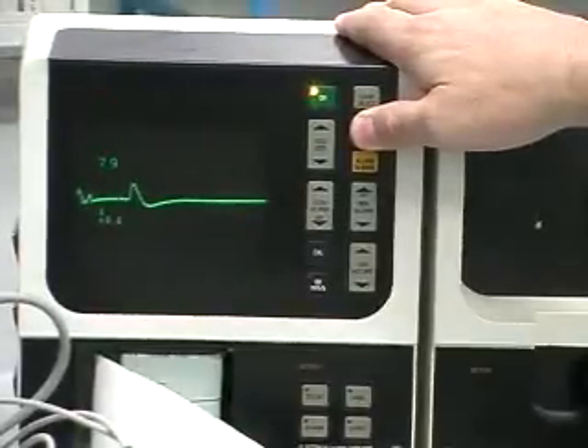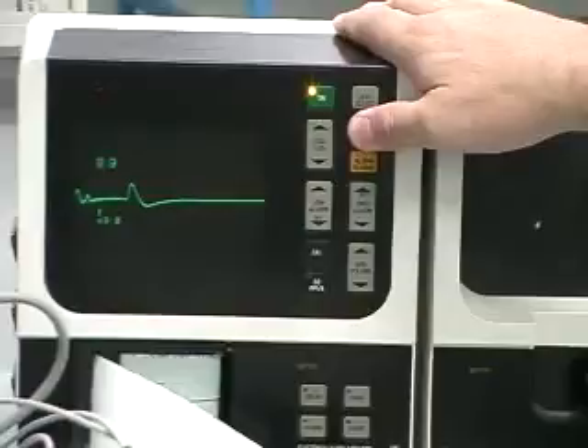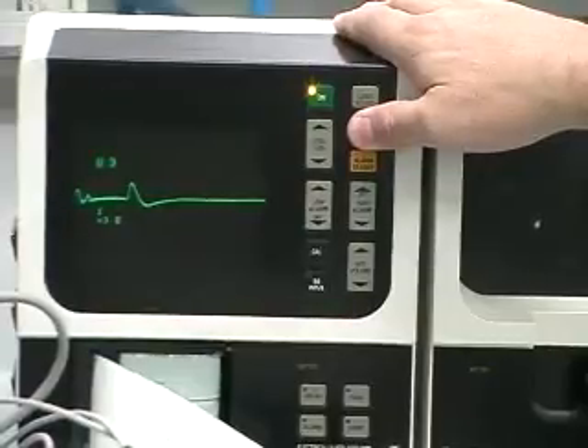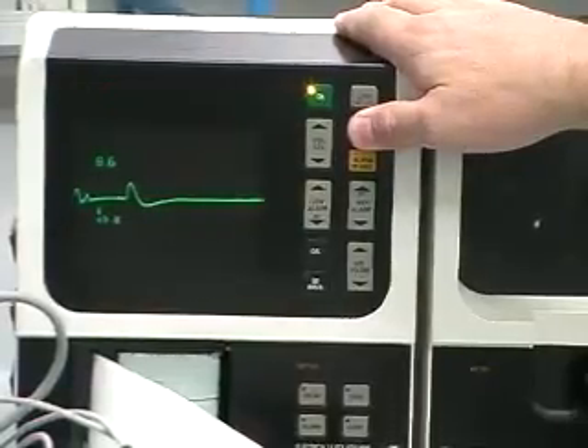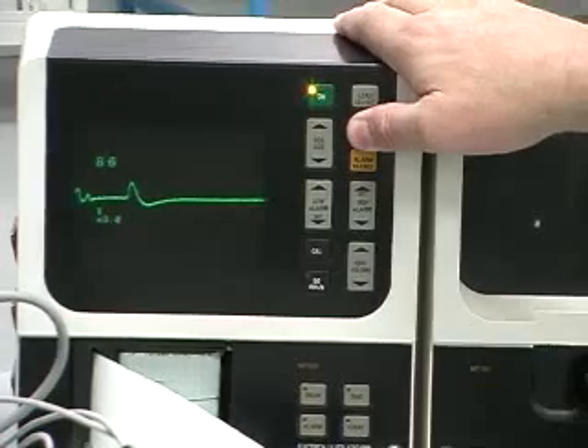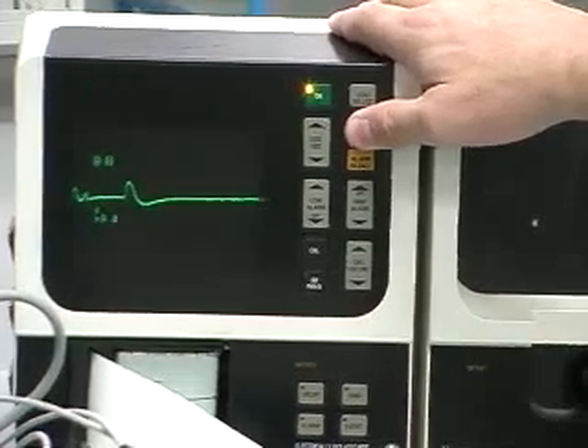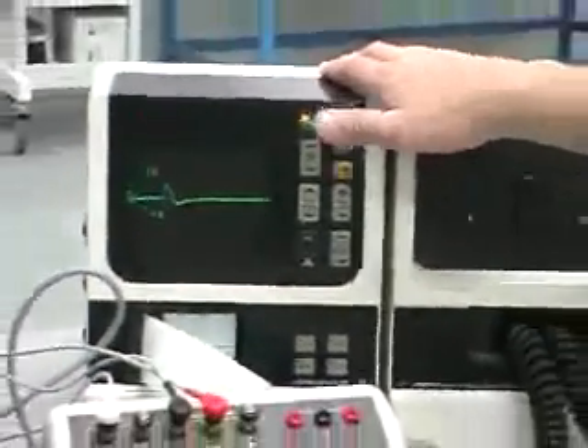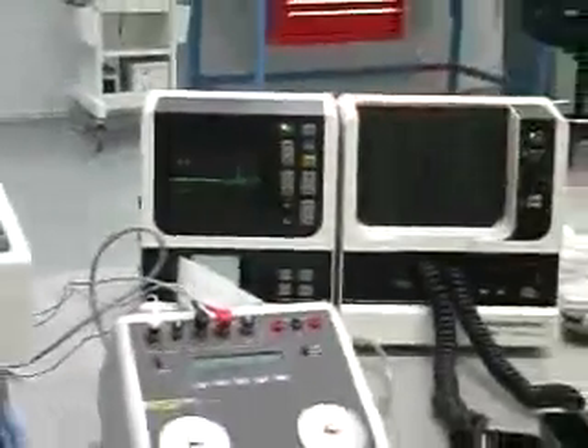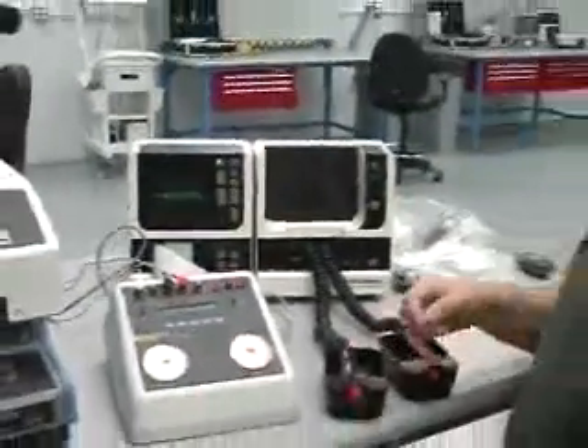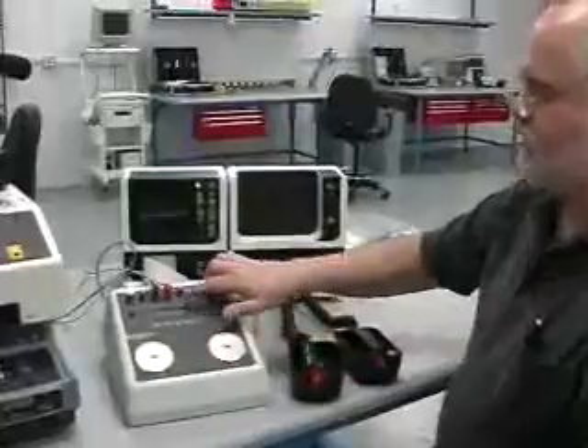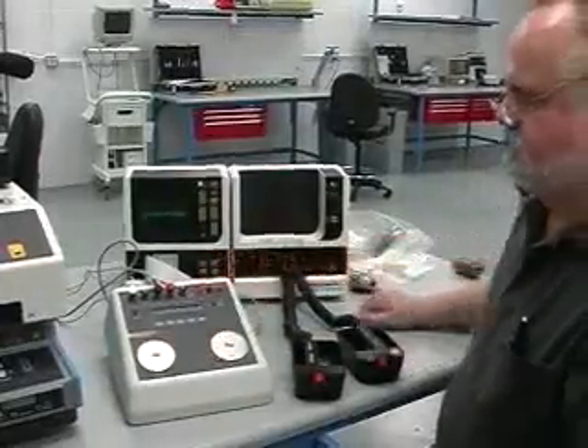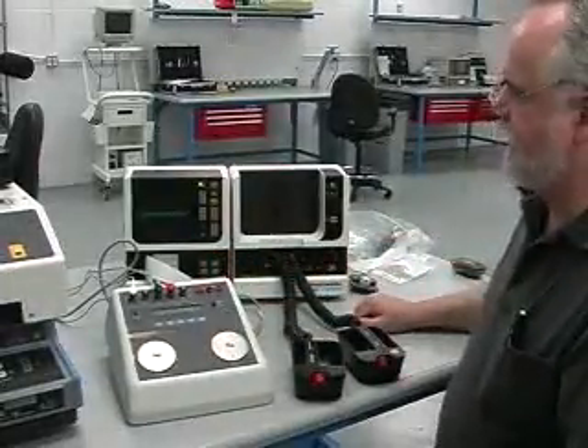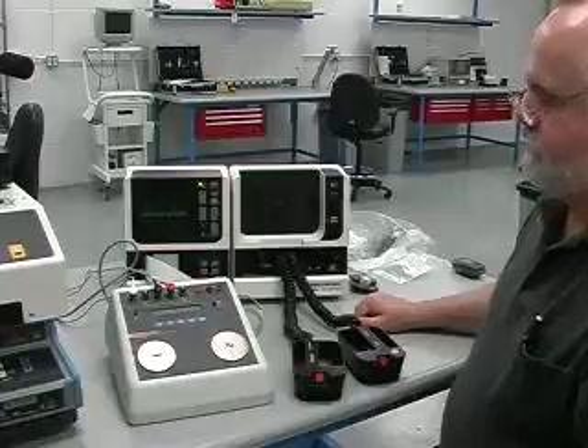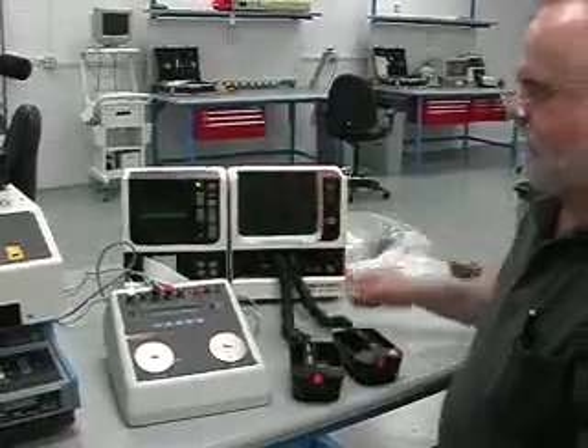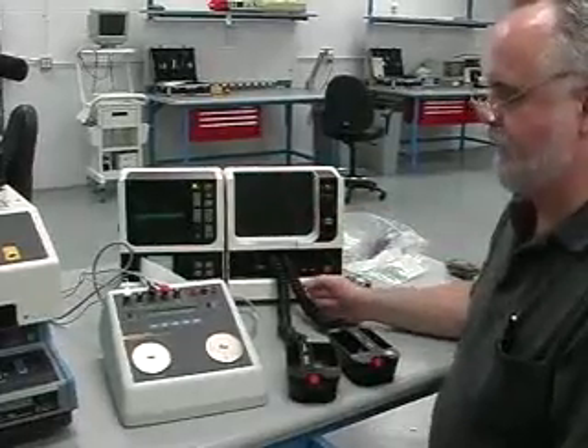and that you are looking at a higher single phase pulse, and you would just be wanting to see that there weren't any major gaps or glitches in the waveform itself. So just another way of checking the waveform quality of the defibrillator. So you have a marker of the actual energy level and a bit of an idea on the waveform quality by looking at that replay.